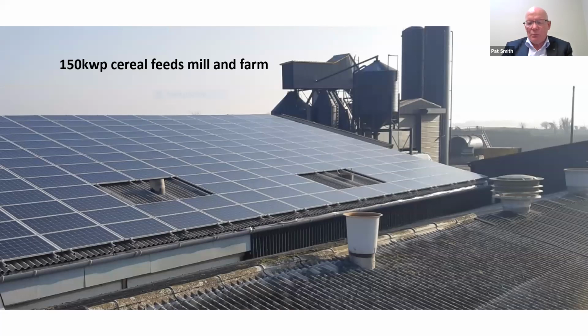The one thing that I would say with horticulture, and particularly for potato farmers, is that in the June, July period the fridges tend to be turned off, albeit that period is shortening all the time. And that's where the grid connection comes in. One thing I would say to the participants: most of your farms probably have their own transformer, and that transformer is going to dictate how much you're going to be able to export to the grid. An awful lot of homes across the country will be sharing transformers.